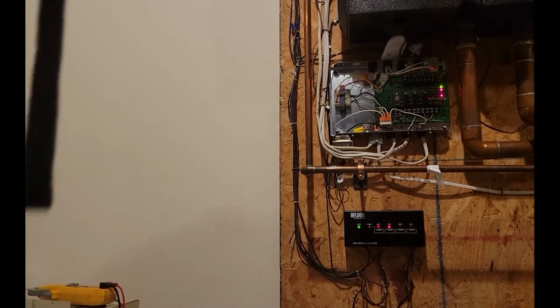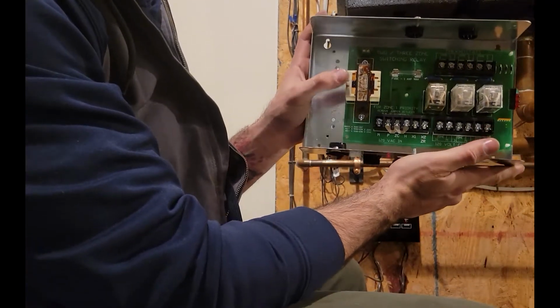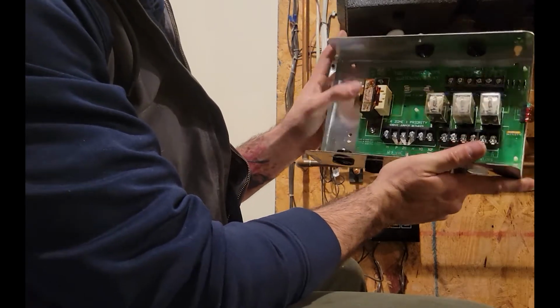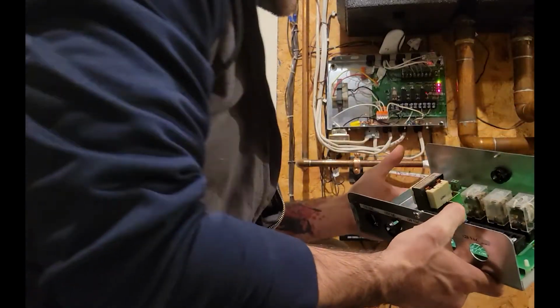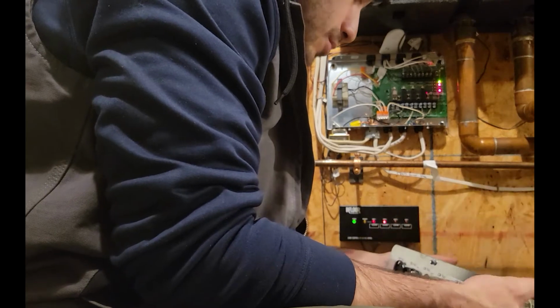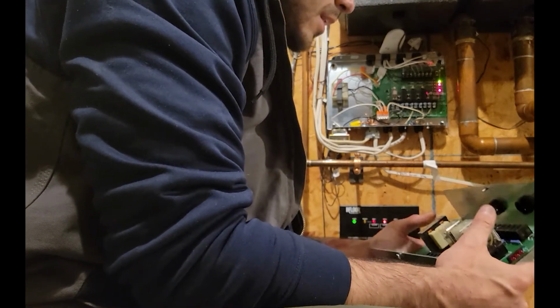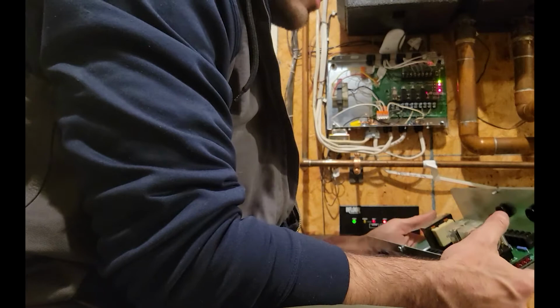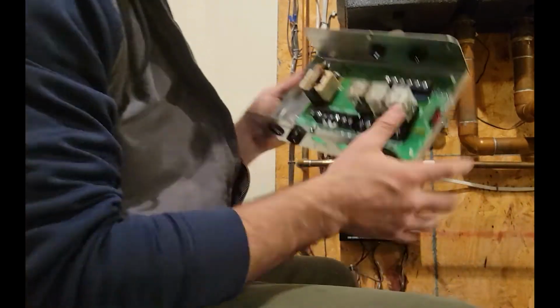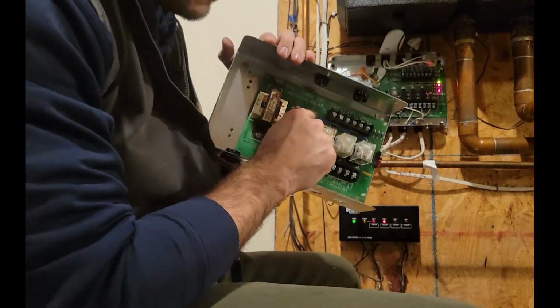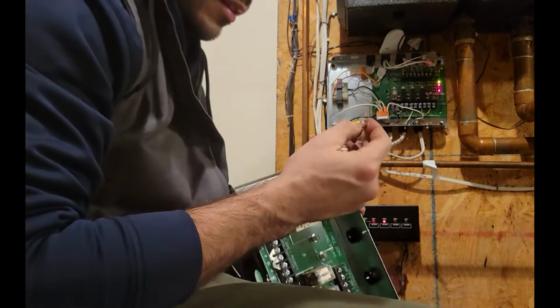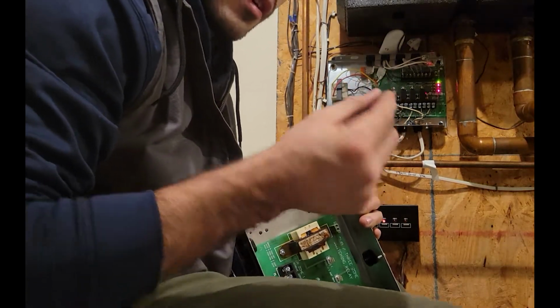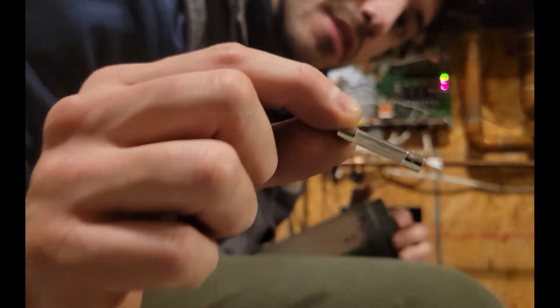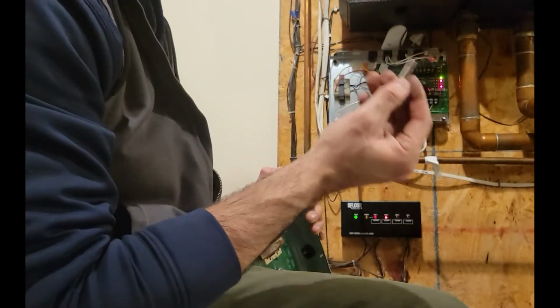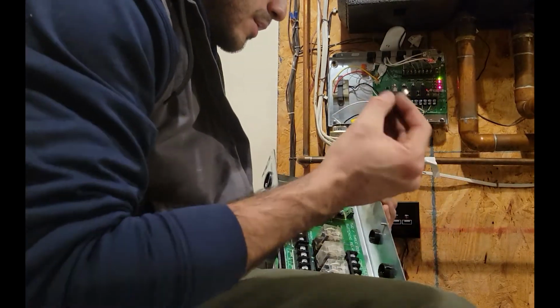So basically, this guy right here is the old box. You can see that it's got some discoloration here. The customer said his electrician, without any tools, without anything, determined that the transformer was bad. He wasn't wrong, right? The transformer was bad, but if you take a look here, there's an inline fuse right here. This fuse was actually popped. Now it's gonna be really hard to see, but the link is broken on this actual fuse. So the fuse is bad.